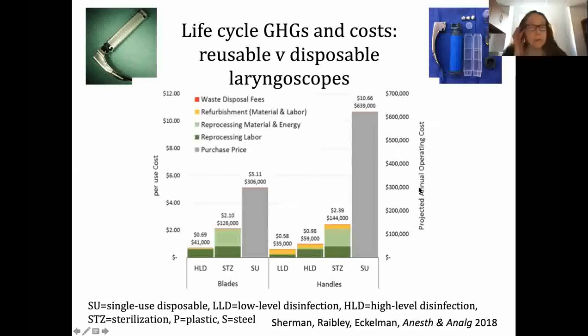By about $700,000 combined. And one of the questions we get is, well, it costs so much to clean them that it's cheaper to go with disposables. Well, firstly, we reprocess about 12,000 instruments a day. This would increase what we reprocess by on average 167 instruments a day, because we're already reprocessing the tongue blades. So between 1% and 2% it would increase. So firstly, we would not have to increase labor in our central sterilization supply department. But even if we did, the institution would still benefit from a cost perspective.